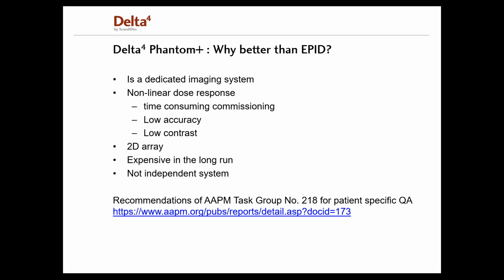So to continue more with comparisons, we will now look at why the Delta4 Phantom Plus is better than EPID. So first of all, the EPID is not intended for dosimetry measurements. It is an imaging system. And for it to be used as a dosimetry system, one needs to do time-consuming commissioning, and this is also due to the non-linear dose response in the system. This then results in low accuracy and low contrast. The EPID is a 2D array system, which requires reconstructions to get the dose in 3D. And we all know that as soon as you apply any kind of reconstructions, you lower the accuracy.